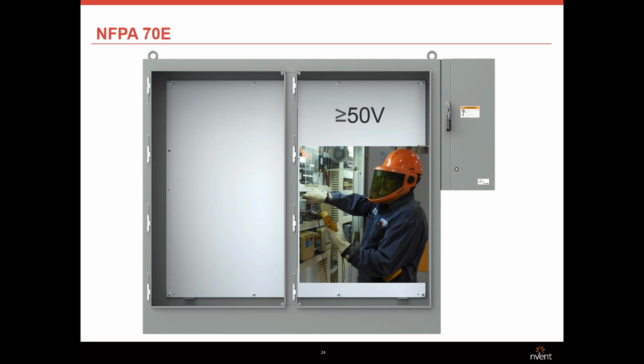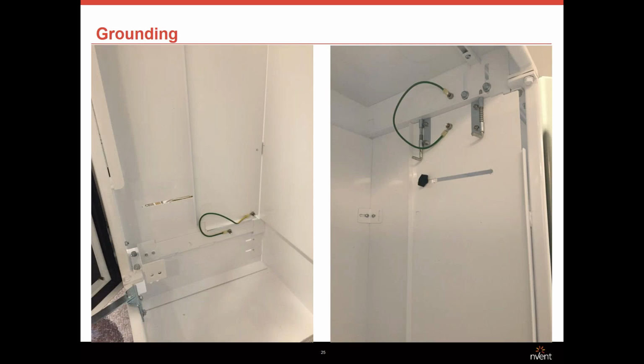I'm moving through this a lot faster than I thought I would, but that's all right. One note I want to touch on is grounding. All barrier panels will need to be bonded to the main equipment grounding circuit per UL 467. One of the things that you will notice here is we have bonding straps on certain panels. Other panels are bonded through the screws, and that is where the bonding is actually happening on those particular parts of the panel.